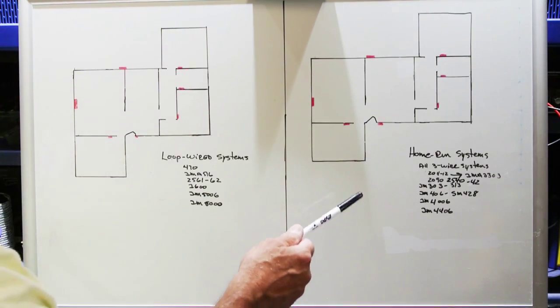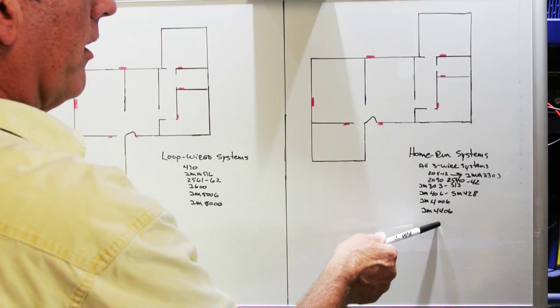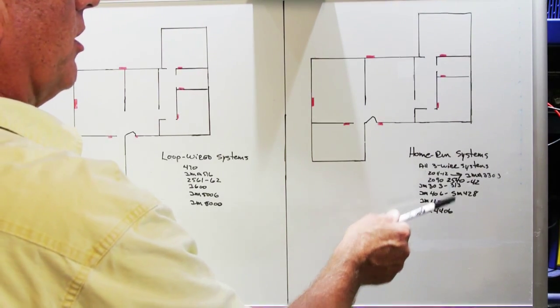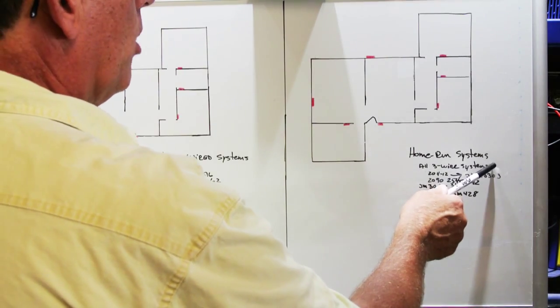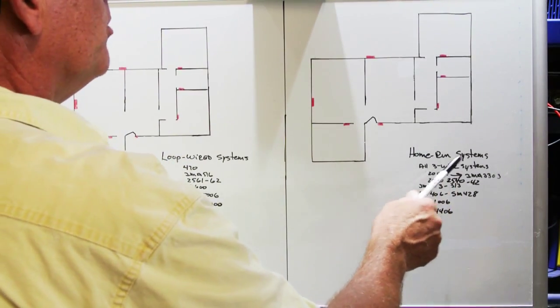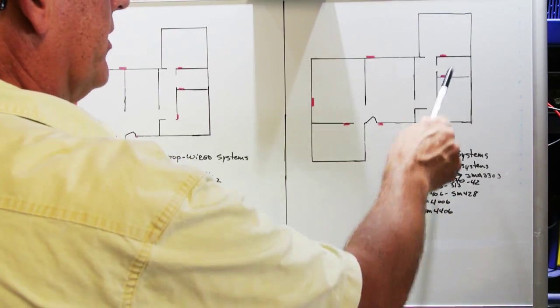There is a rule about how systems have to be wired. Equipment, all of these models and more that were designed to be installed with home run wiring can only be home run. They cannot be loop wired. You cannot have more than one remote station on the same cable.